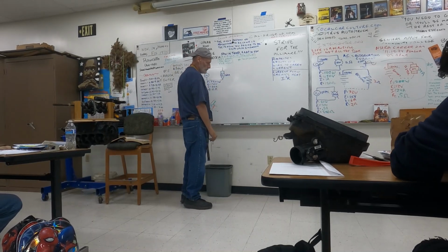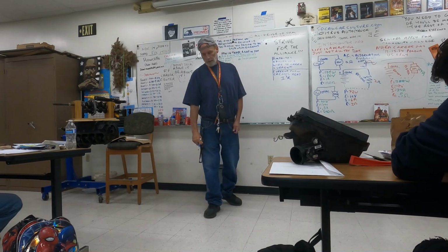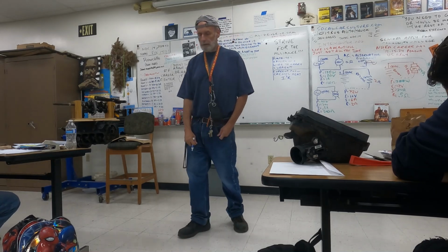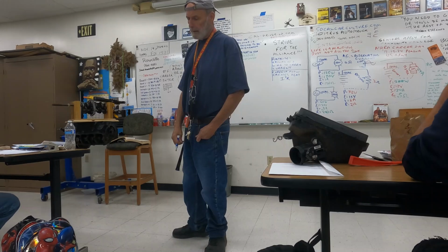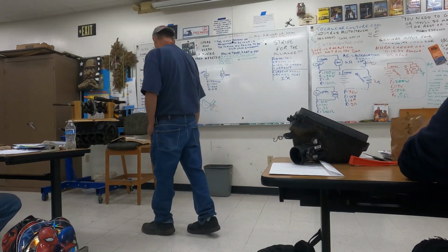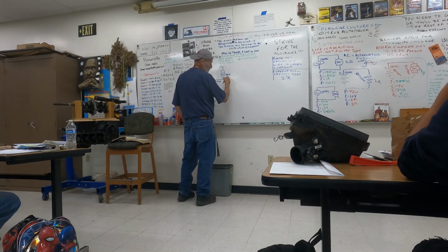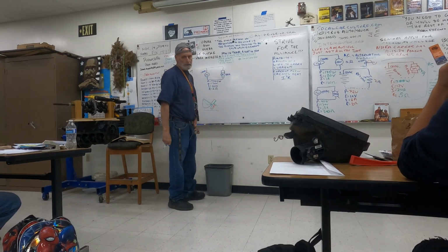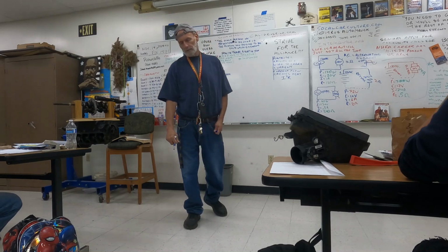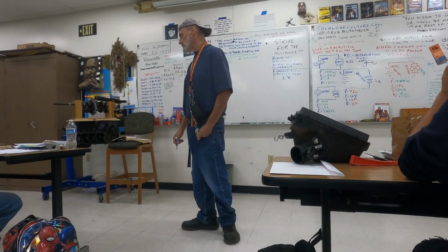Watts, because of power, right? That's right. So if I was running an air conditioner or some big thing like a dryer on 120 volts, first of all, you're probably not gonna find a 60 amp circuit at 120 volts. They just don't do it. Why? Because the wire size would have to be huge.